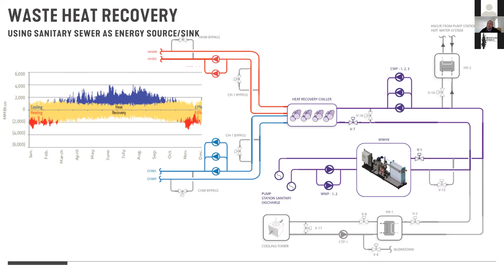But a key strategy, before we start looking for all these other places to go get energy, is trying to find ways that we can recover our own waste heat. Whether that's the sewer water leaving my building or my own rejected heat that normally would go to a cooling tower. Finding that middle band of heat recovery is actually the highest place that we can put our efficiency dollars because our COP is going to be between 6 and 9 when we're doing full heat recovery, and we don't really care what's going on outside of the building.